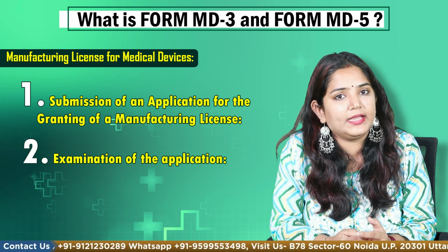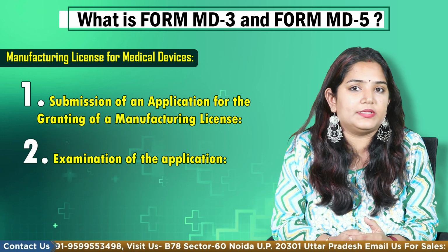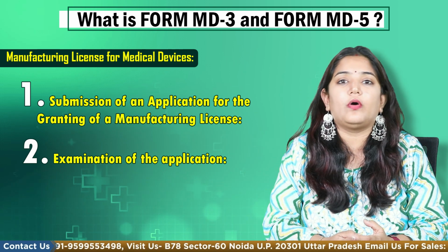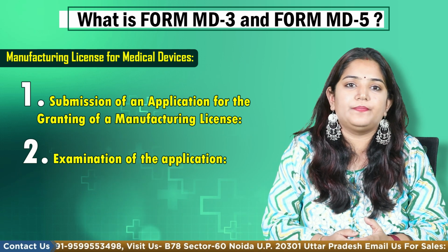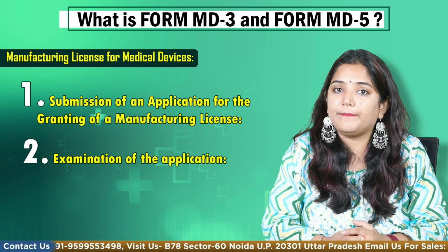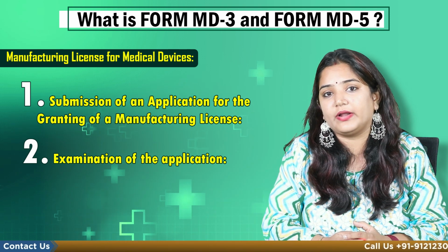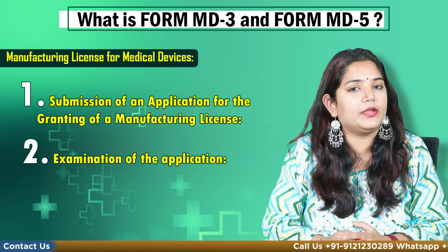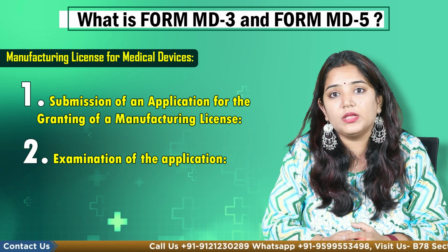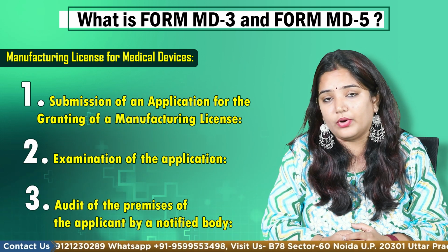Second, the examination of the application. In the event that any deficiencies or inconsistencies are discovered, a query must be submitted. After receiving a response to the query from the applicant, the next step in the process will be taken. In the event that the application is deemed to be in proper order, it will be processed for factory premises audit by a notified body in accordance with the Medical Device Rules. Audit of the premises of the applicant by a notified body.